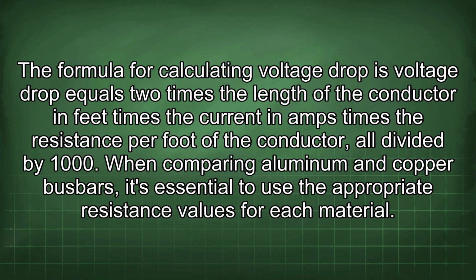The formula for calculating voltage drop is voltage drop equals 2 times the length of the conductor in feet times the current in amps times the resistance per foot of the conductor, all divided by 1000. When comparing aluminum and copper busbars, it's essential to use the appropriate resistance values for each material.